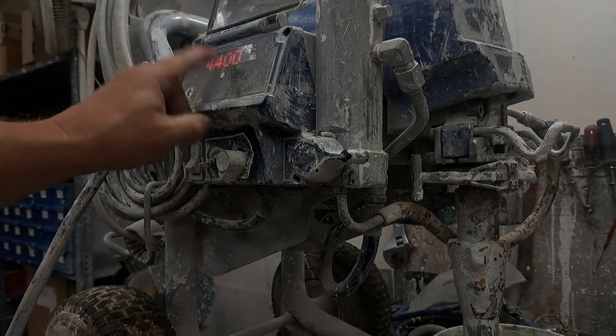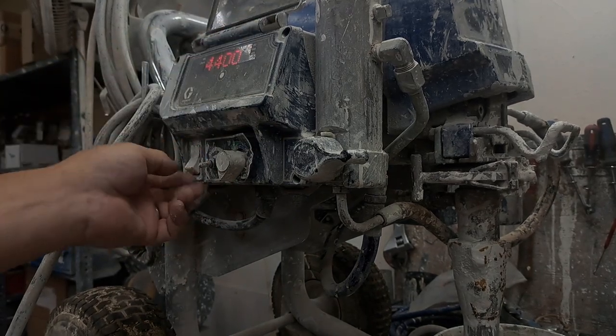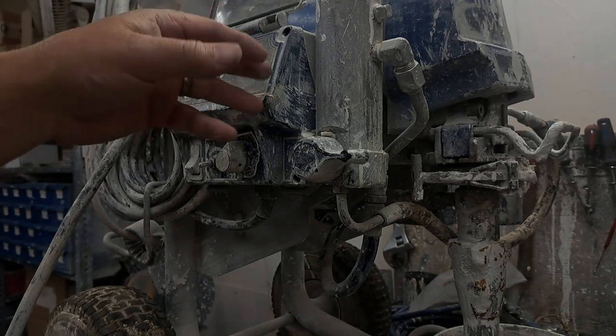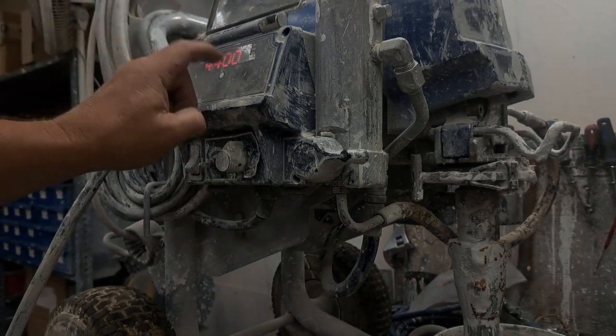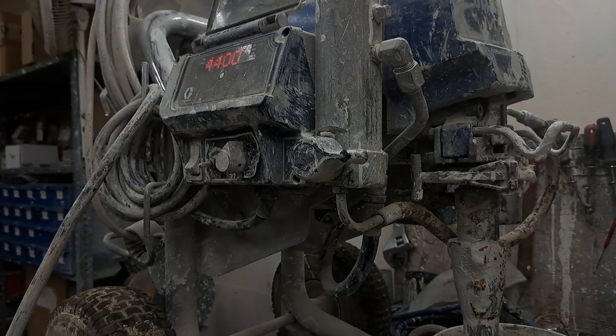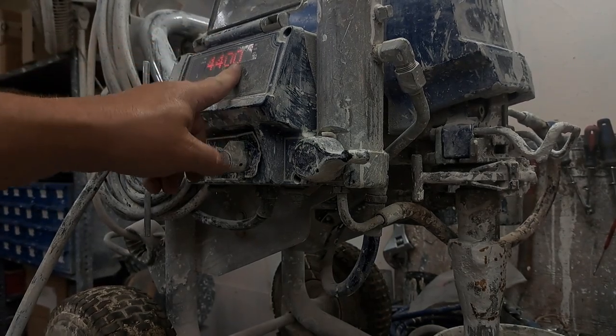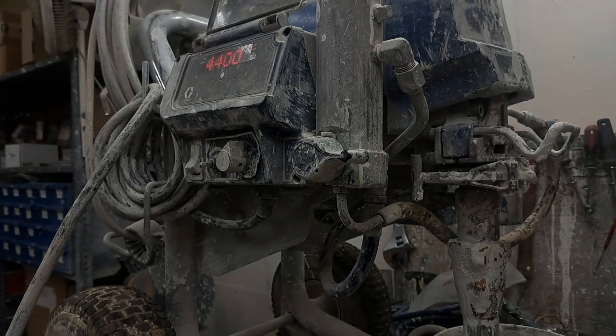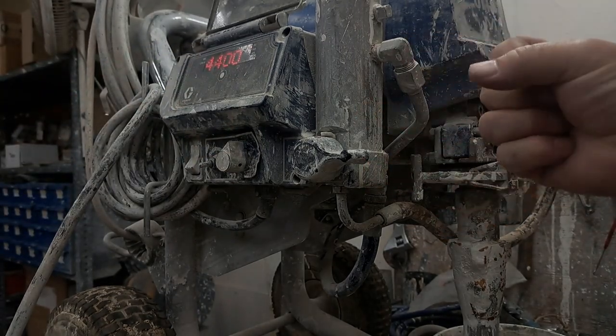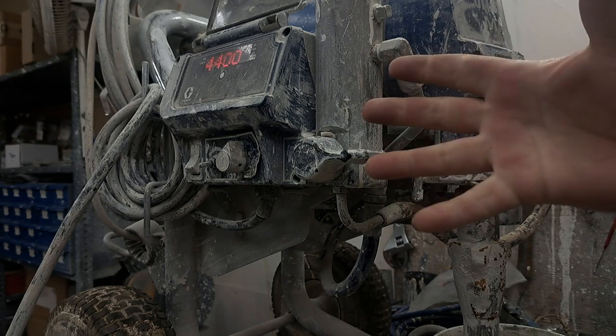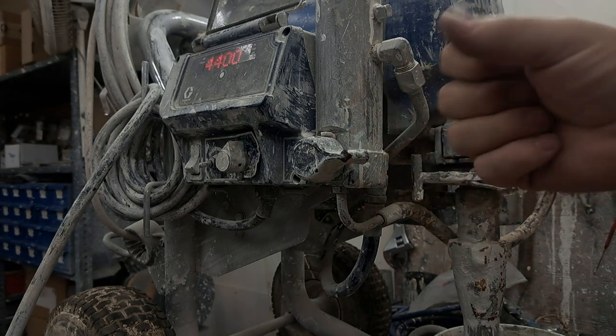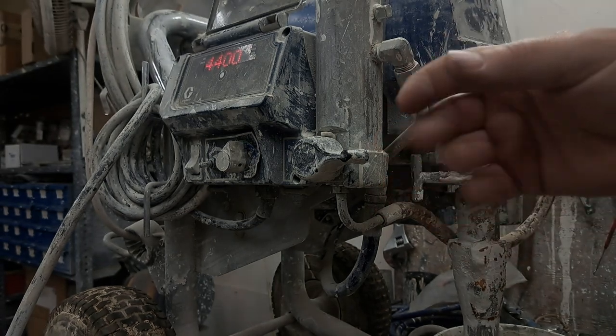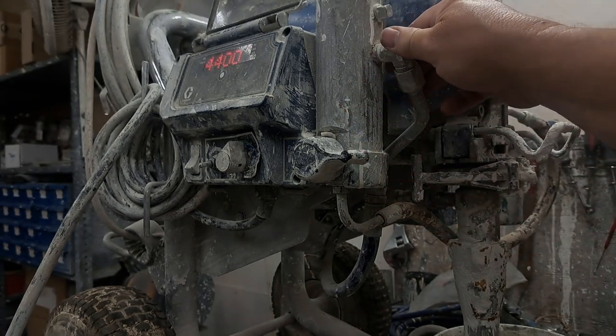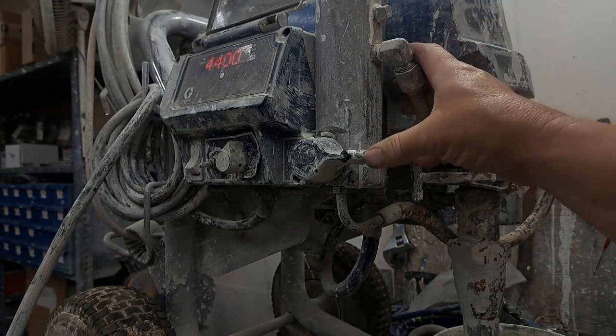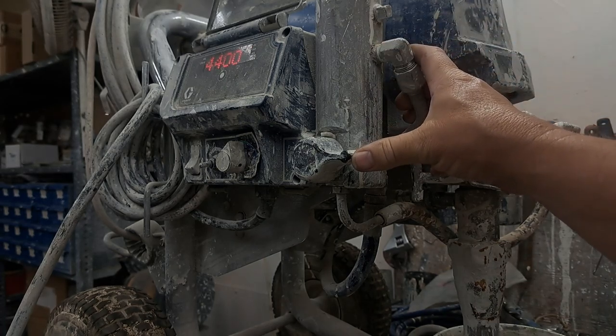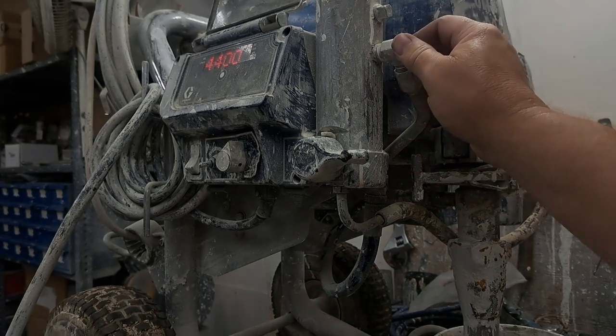Now, if you don't have a display like this, your machine, you turn it on like we just did, turn the pressure up and nothing happens. First thing you're gonna do is take this cover off and look at the board. On the inside is gonna be some LEDs. The LEDs might be red, might be green. They're gonna flash. So it'll flash, flash, flash, pause, flash, flash, flash, pause, and it'll repeat 2 or 3 times depending on what exactly is going on. Though it may be more than that, but 2 or 3 is going to indicate a transducer. But those number of flashes, if you look them up, it's going to tell you.